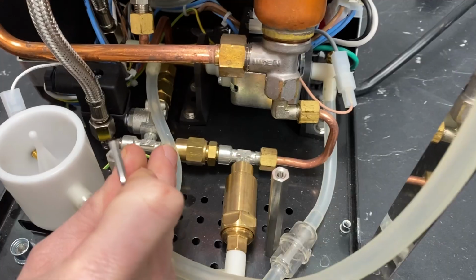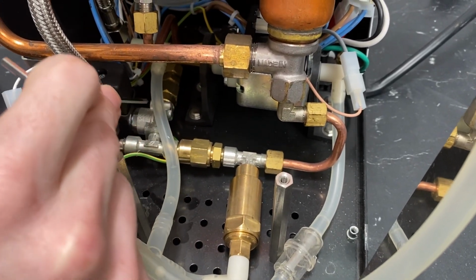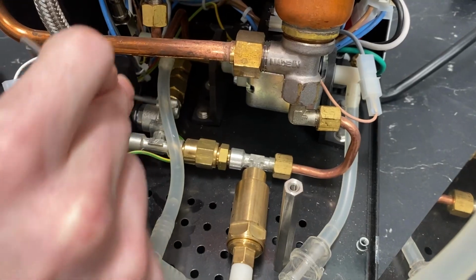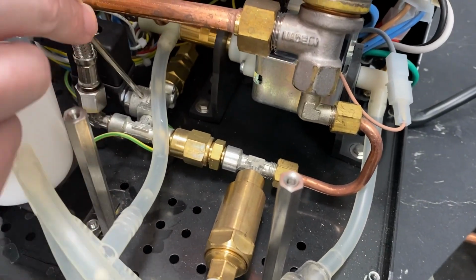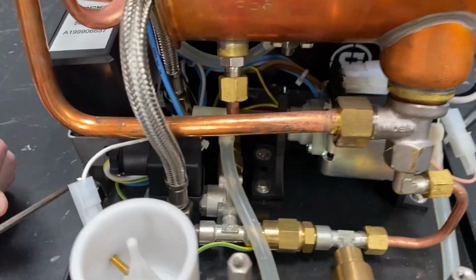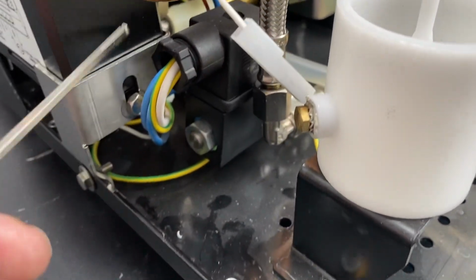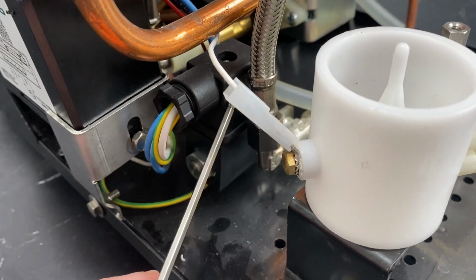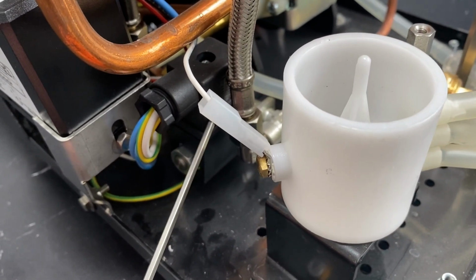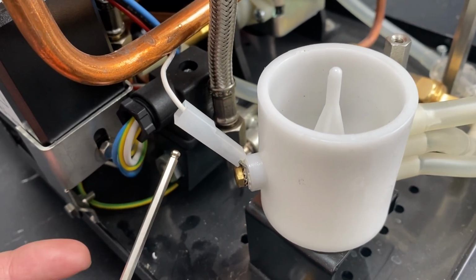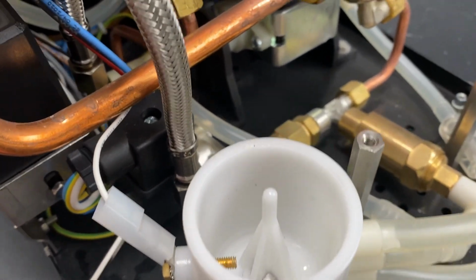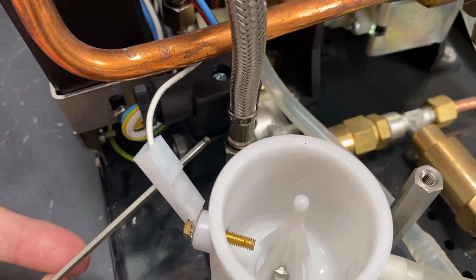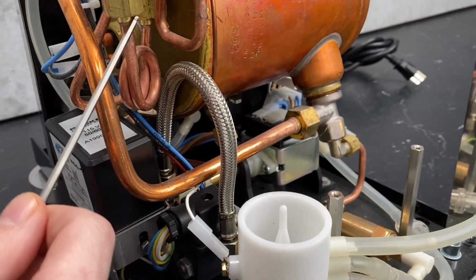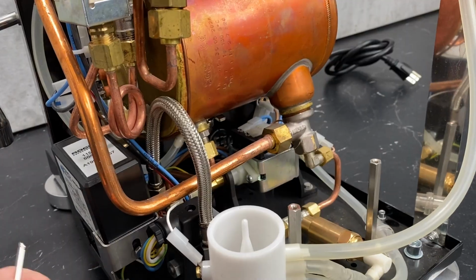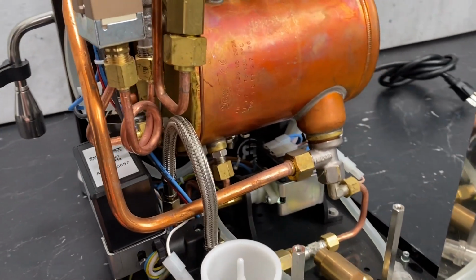So we're going to start off talking about the fill for the steam boiler. So that's going to go this way. It stops right here at the fill solenoid. Now, if you see, there's your solenoid. Looks a little bit different than some. It has this cap for the electrical connections, which is really nice because it makes sure that if you ever have to take things apart, all your wiring is correct, and it seals against moisture, which is really nice because your connections are facing up right below a boiler with areas that could potentially at some point in the lifetime leak. So if it leaks down on here, that gives a lot of extra protection for it.